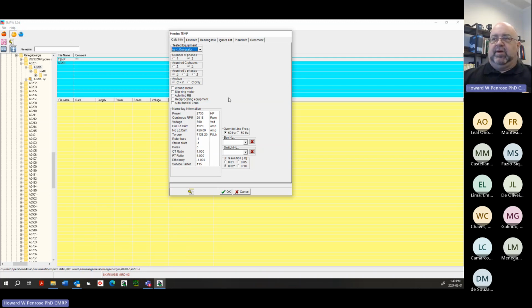It is going to do something that I really hate. It automatically goes and says this is about 1/4. I will always change that to some number that's lower. If you are doing a yaw motor or something, you can always change this also to a fraction. You can put 0.01 there. That basically sets the base load. If I'm doing continuous monitoring, or if I set it up in the tower and I wanted to collect data, you want that current to be less than what your unloaded current is going to be for the tower, so it collects data.